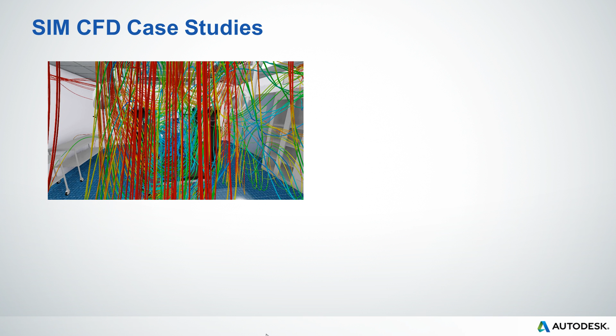The impact of thermal plumes above heat dissipators can be explored by reviewing temperature results. And here we can see in this image airflow traces showing a lot of recirculation of air around the operating table.